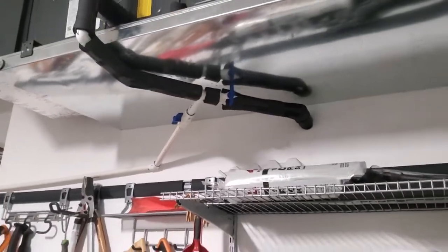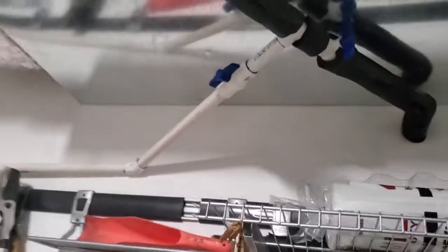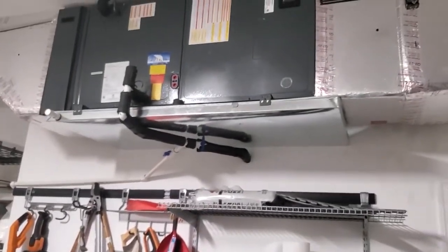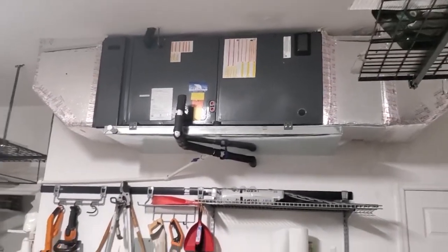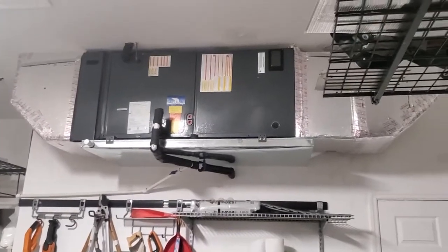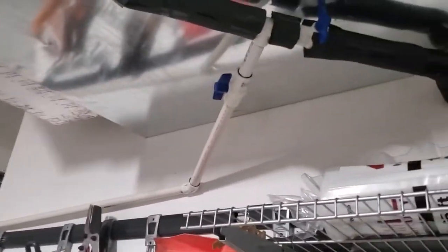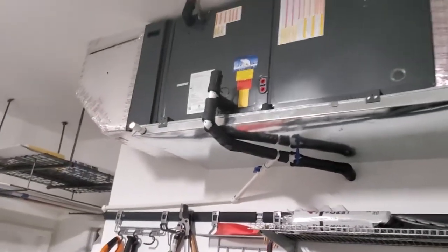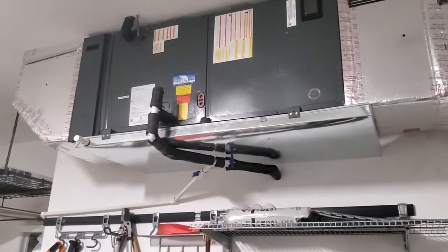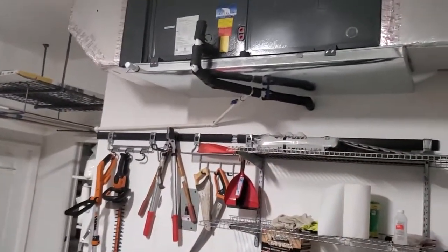If I'm going on a long vacation and leaving the house for a long time, I'll open both valves so if one gets clogged, there's an auxiliary exit. That should last a year or so before it needs to be cleaned out. What do you think? Is there something I'm missing? It just boggles my mind how they'd use a limited three-quarter-inch pipe — it should be at least an inch if it's going through the wall like that, because of condensation buildup and bacterial goo. Anyway, I really like my clean install — what do you think?